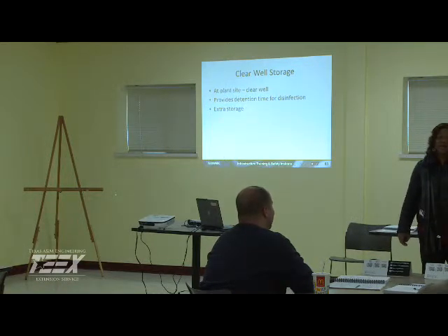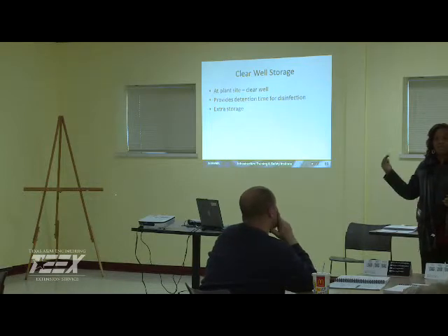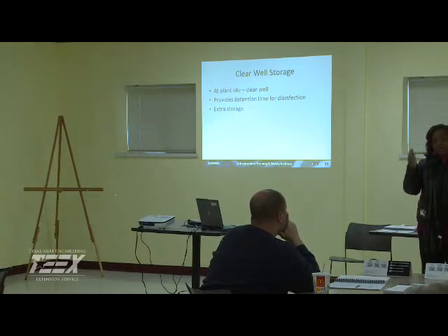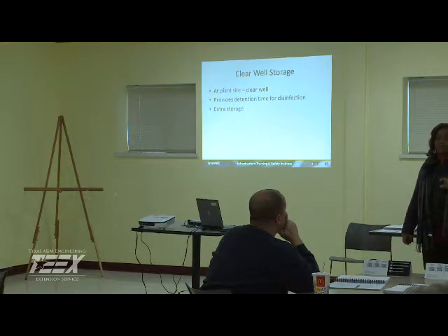It's gone by. Now, when you look at chemicals, there's a way with some of the chemicals to get in there and test the effectiveness immediately. The residual is there, so I know the demand has been met, and I'm good to go as long as I'm at the minimum level that they say I should be at, which is 0.2 or 0.5 combined.